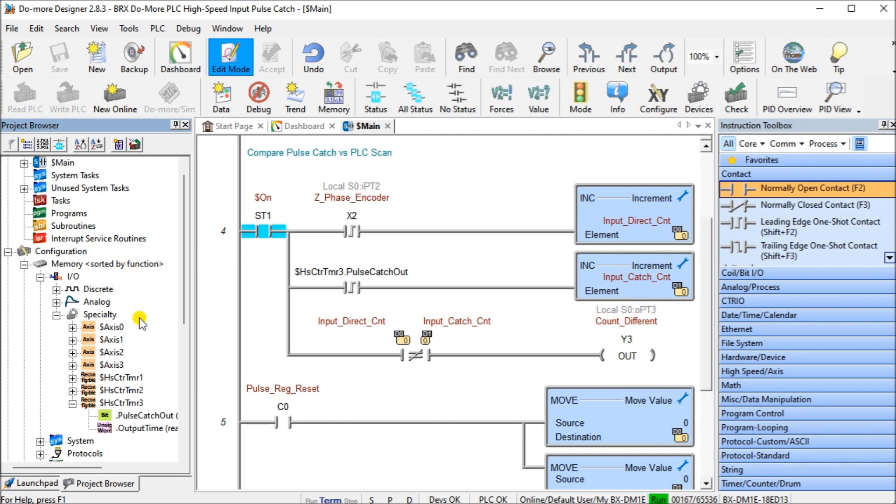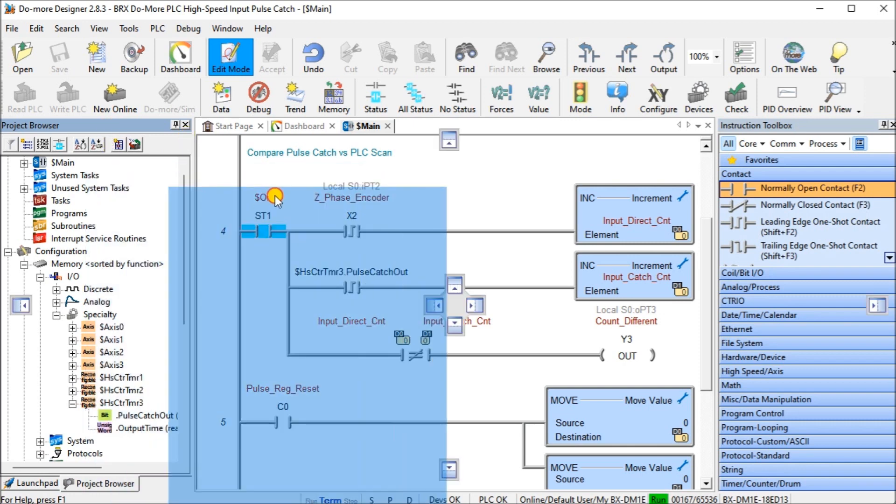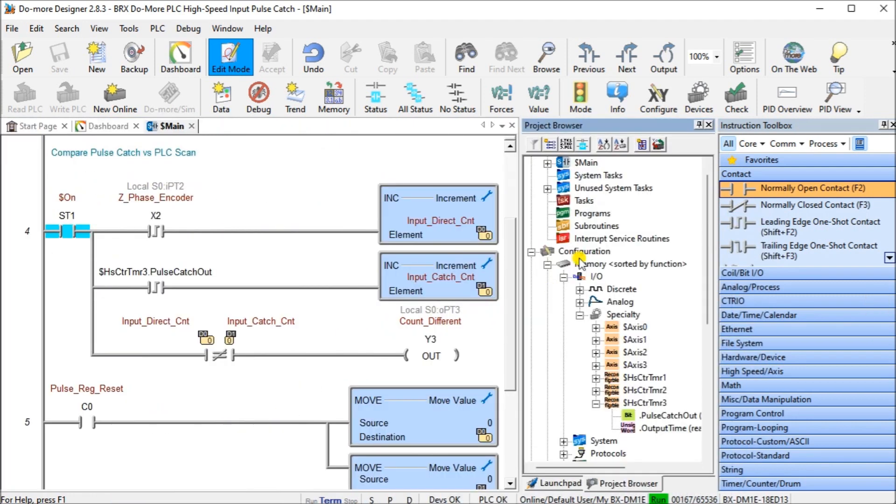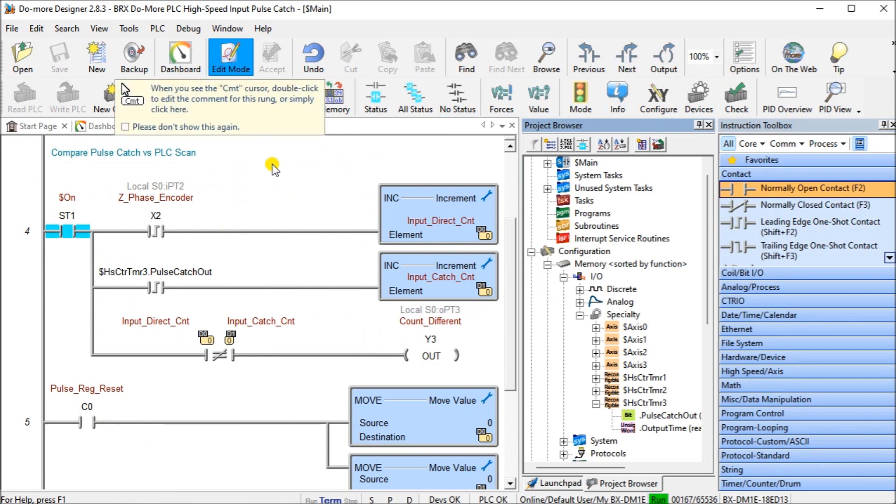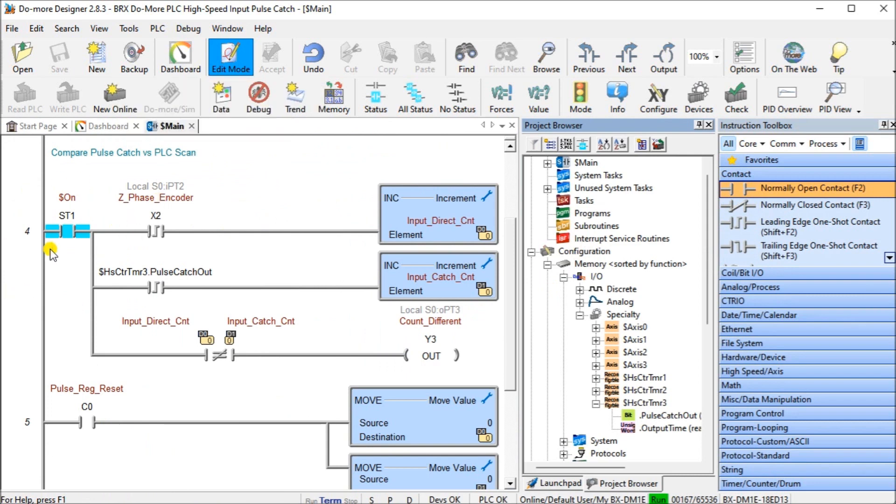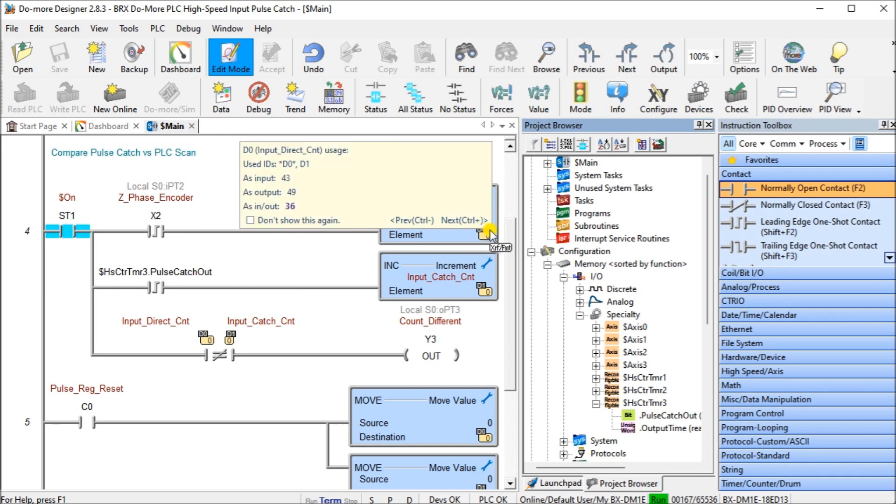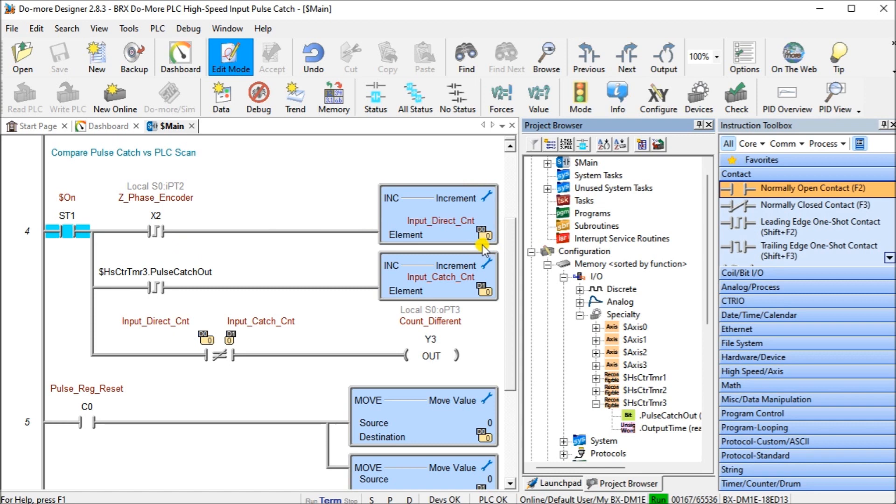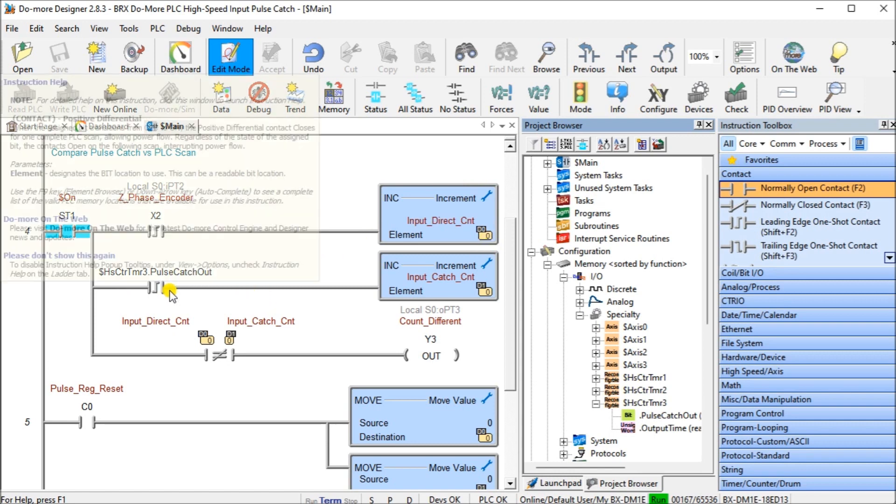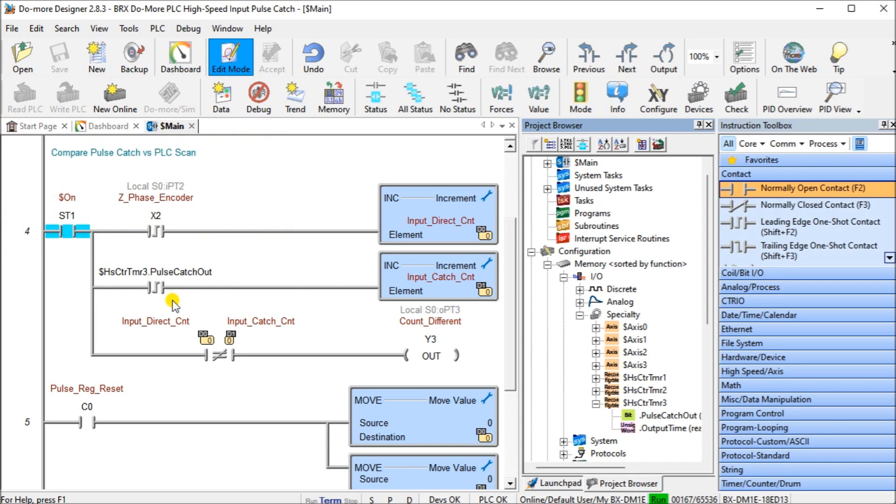Looking at the program, you'll see that we have added a couple of different rungs. The first one, we have an always on flag. We have our Z phase of our encoder coming directly into the PLC, and it's going to count up on D0. So it's going to increment that every time we have a pulse.